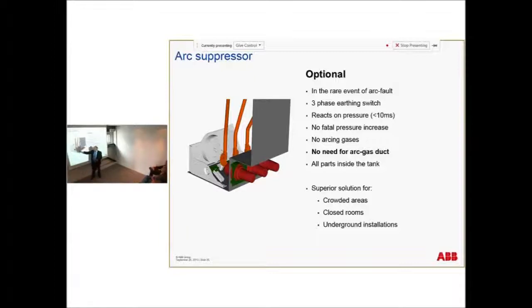We have a separate device with a membrane, which is linked to a switch. And we call this an arc suppressor. If there is a failure in the switchgear, let's say you stand in front of the switchgear, the failure can be inside the SF6 compartment, or it can be in the cable compartment. If there is a failure inside the SF6, where the customers are most worried, we can build in this arc suppressor. This membrane will act very, very quickly.